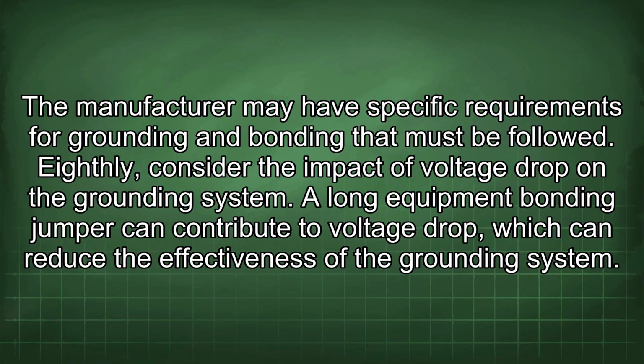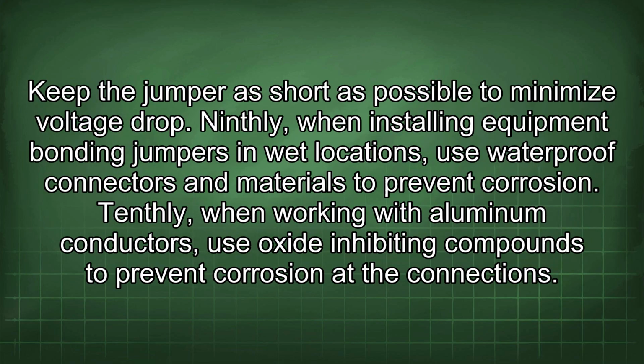Eighthly, consider the impact of voltage drop on the grounding system. A long equipment bonding jumper can contribute to voltage drop, which can reduce the effectiveness of the grounding system. Keep the jumper as short as possible to minimize voltage drop. Ninthly, when installing equipment bonding jumpers in wet locations, use waterproof connectors and materials to prevent corrosion. Tenthly, when working with aluminum conductors, use oxide-inhibiting compounds to prevent corrosion at the connections.